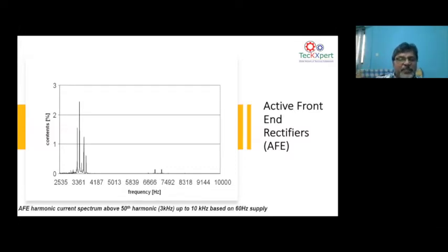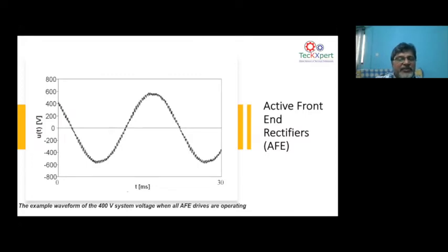Go to the next slide. With the active front-end drive, you can see how the voltage looks. It carries a lot of noise. That is why the voltage waveform has a lot of small ripples on the top. These are all high frequency currents coming from the active front-end drive. Sometimes these noises can cause problems to electronics. If the grounding is not proper, these noises can pass through the ground and come to your electronic cards and increase the DC voltage there, and the electronics can fail. So this is how active front-end drives create problems for sensitive electronic devices. Go to the next.